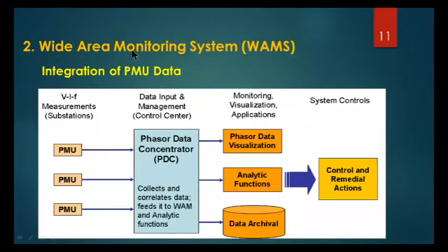In the wide area monitoring system, we have a phasor data concentrator, or PDC, which collects input from PMUs such as voltage and current magnitude, phase angle, and frequency from various substations. It collects and correlates the data, feeding it to WAMS and analytical functions such as forecasting, power flow analysis, stability analysis, and assessment.